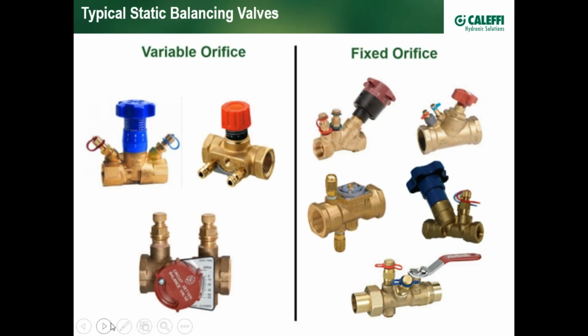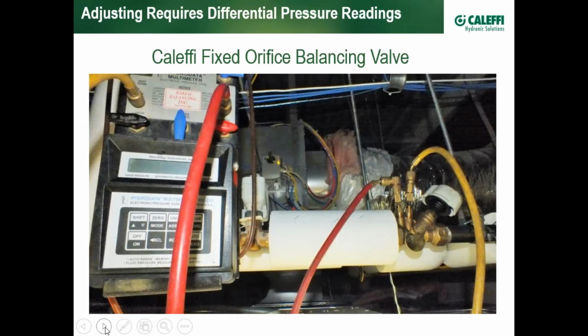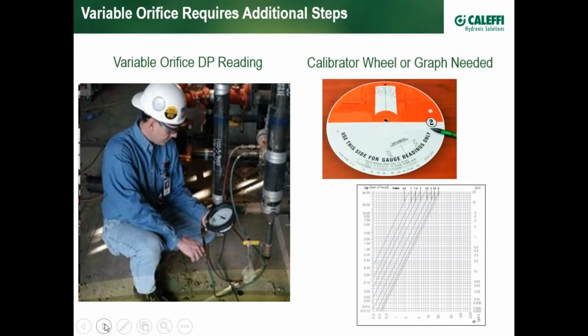Whether variable or fixed orifice, they do require a pressure drop reading across the two ports to determine flow rate through the valve and allow the contractor to adjust the flow rate to the designer's specification. Here is a contractor doing such a procedure on a Caleffi fixed orifice type balancing valve. A differential pressure gauge or manometer is used. There is training and skill needed to calibrate and operate this equipment and set the flow rate accurately, whether fixed orifice, or variable orifice, as being shown in this photo. By the way, variable orifice requires a little bit more effort because the flow coefficient of the space between the pressure ports changes as one adjusts the valve.